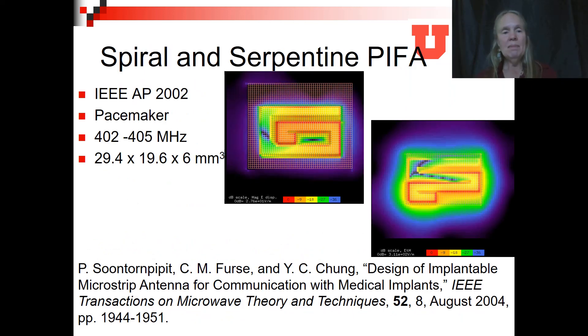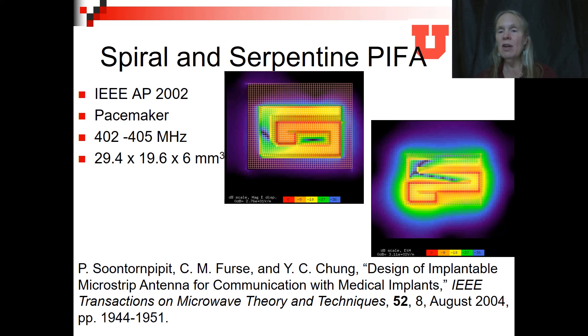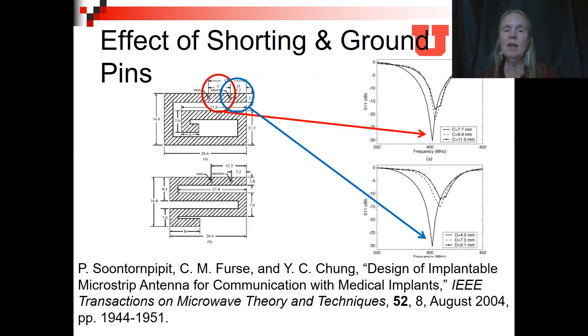The spiral and serpentine PIFA had interesting current distributions. In the spiral case, strong current was seen at the end of the antenna — unusual for a dipole — because of cross-coupling between the arms. In the serpentine case, there is less of that behavior. The frequency chosen was 402 to 405 megahertz, good because an antenna could still be built small enough to fit on the pacemaker while being low enough in frequency to transmit outside the body. We also considered the effect of the shorting and ground pins: the red pin is the feed pin, the blue pin is the ground or shorting pin, and moving these changes the resonant frequency and the depth of the S11.